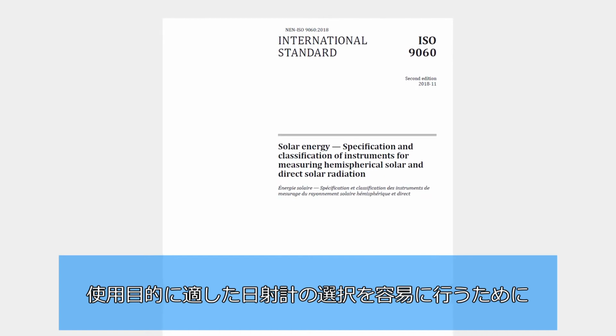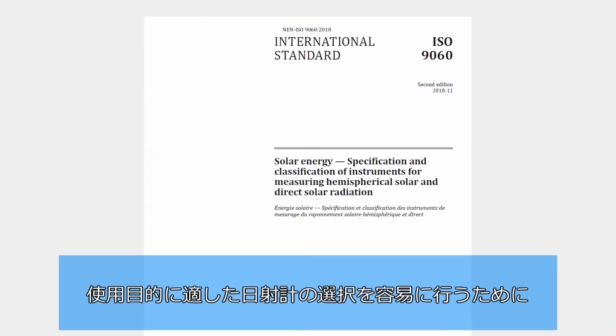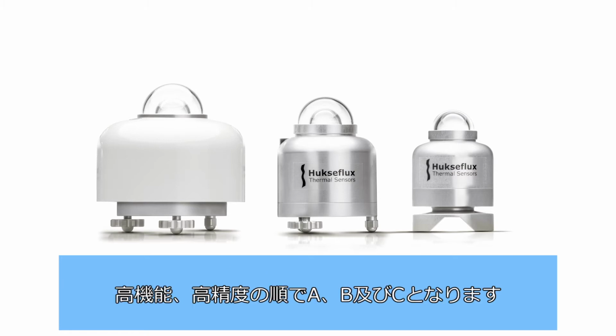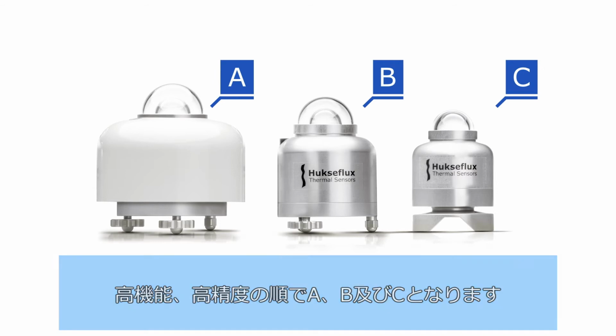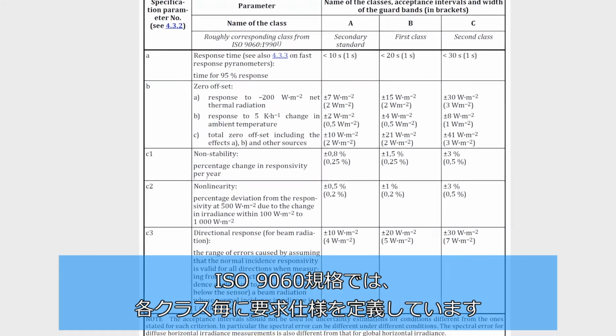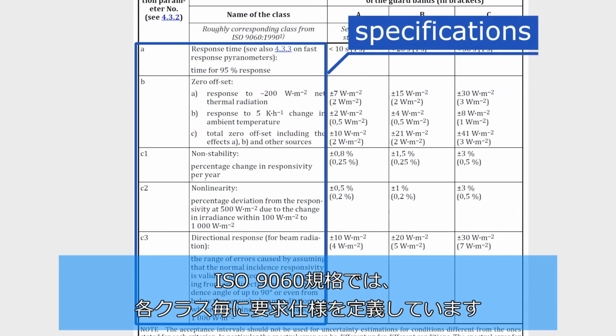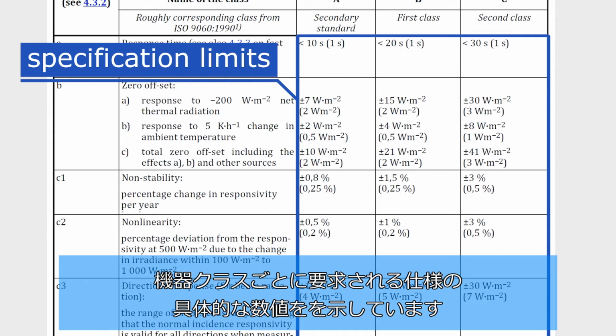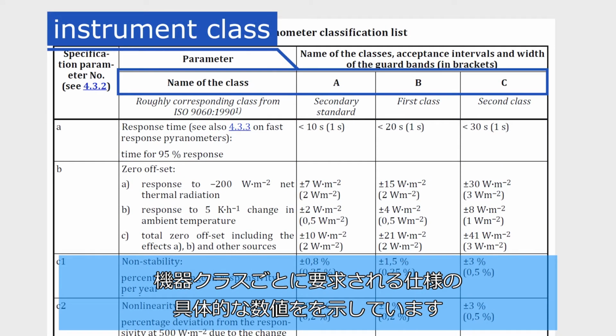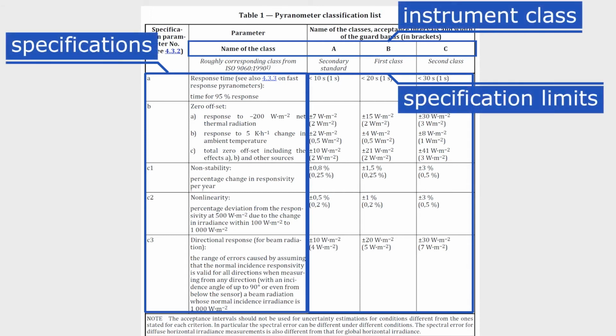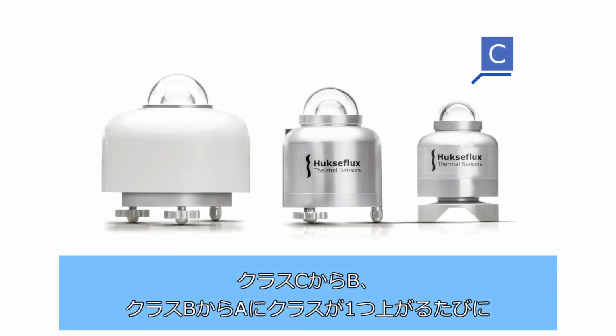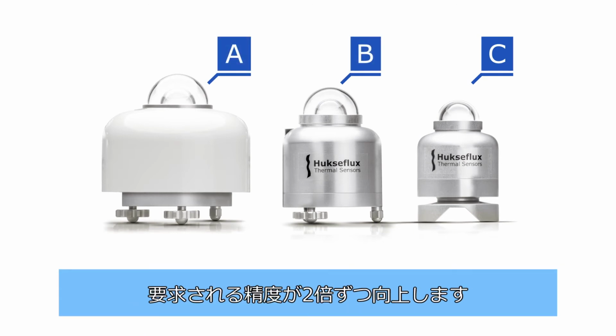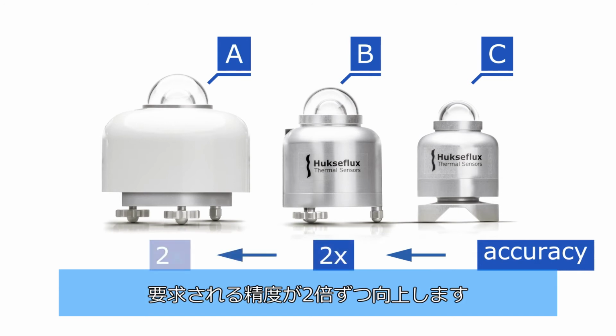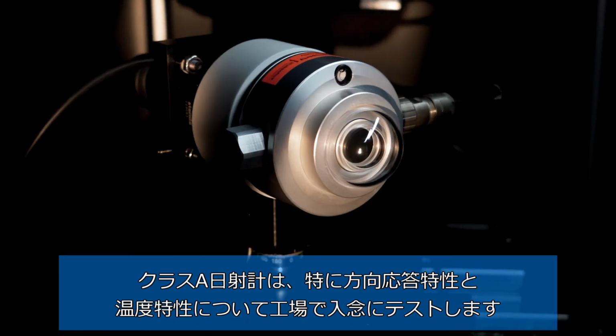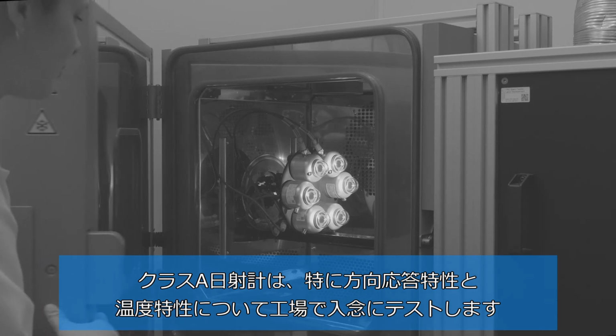To facilitate the choice of instruments, the ISO 9060 standard defines 3 different pyranometer accuracy classes: A, B, and C. The ISO 9060 standard defines specifications and gives specification limits per instrument class. From Class C to B and Class B to A, the achievable accuracy improves with a factor of 2. Class A pyranometers are subjected to elaborate factory testing of directional response and temperature response.